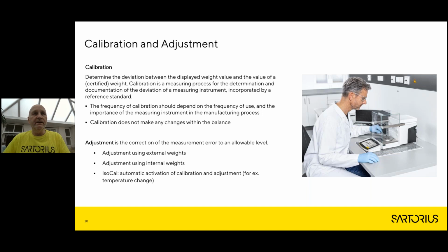Now, the fourth parameter that we're going to look at is the sensitivity of the balance, or what we would call calibration and adjustment. In other words, the slope of the balance between 0 and capacity of that balance. A small misconception about calibration and adjustment: people talk about calibrating their balances. Well, yes, calibration of the balance is to determine the difference between the slope where it should be and the slope where it is. In other words, that sensitivity error or slope error. Is the slope too steep or is it too low?